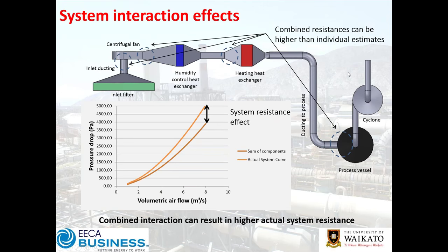The answer is what we refer to as a system resistance effect. This acknowledges that between each of those components we've got additional losses not fully captured individually — losses around the fan inlet ducting, at the fan outlet, transitions in the duct beyond what we'd anticipate, and inlet and exit effects of process vessels and cyclones. These sum up to additional pressure drop, and when you measure individual components you don't necessarily capture all of these additional losses.